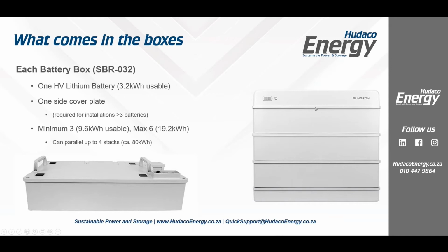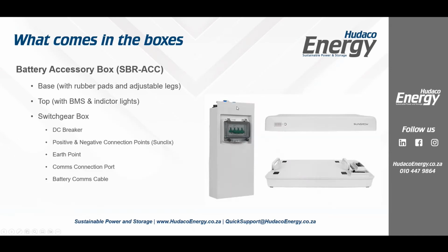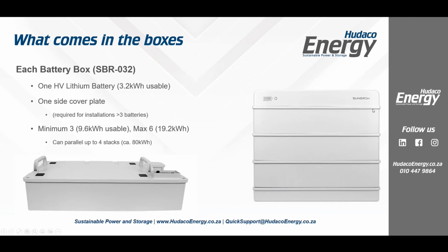Okay. There's also a cover plate. Now, if we install 3 batteries, you won't use the side cover plate. If we go more than that, in other words, if we go up to 6 batteries, on the top 3, you will clip the cover plates in, and those clip on the side here just to cover everything and make it look neat, where this piece, so your protection, actually sits over here and is 3 batteries high. It's exactly 3 batteries high. So the reason we have the cover plate is your next 3 batteries would require that.